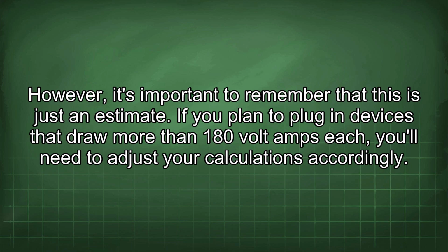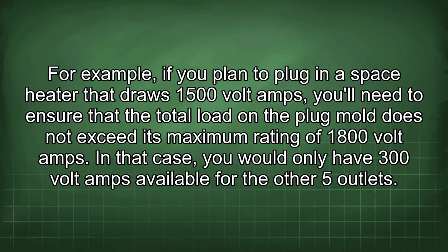If you plan to plug in devices that draw more than 180 volt amps each, you'll need to adjust your calculations accordingly. For example, if you plan to plug in a space heater that draws 1500 volt amps, you'll need to ensure that the total load in the plug mold does not exceed its maximum rating of 1800 volt amps. In that case, you would only have 300 volt amps available for the other 5 outlets.